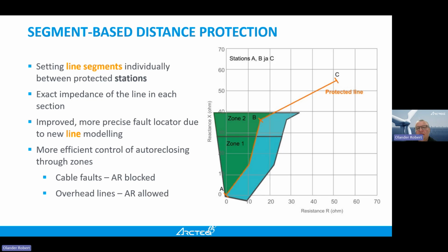In a typical distance protection, you make an assumption, you make an estimation of the impedance on the line. So when you go to a certain spot on the line, you will have an impedance which is close to the actual one on the line. But what we have done different is that you can actually feed all these different line segments. If we have a cable, we have a reactor, we have an overhead line, we have another overhead line, you will put the exact distance, the exact meter of this type of cable and what the impedance is. So on each spot of the line, you will have the exact impedance that is there. So if you have a fault there, it will react according to the impedance and you will know exactly what it is. So it will be more accurate. You will have better accuracy on fault location and also be able to do the control better.